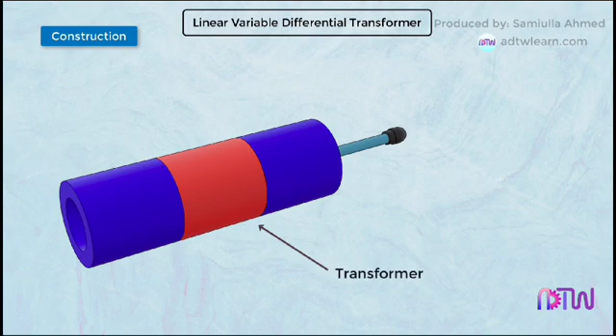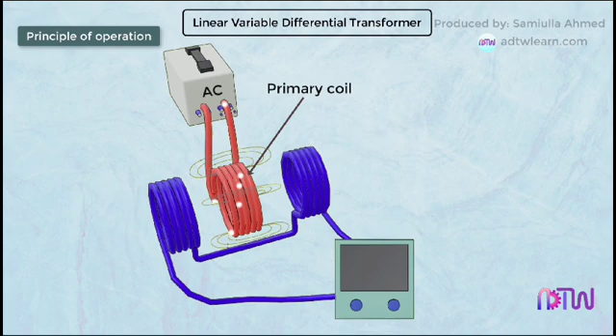Construction: a typical LVDT consists of a cylindrical transformer with a primary coil and two secondary coils, and a movable soft iron core. The primary coil is placed between the two secondary coils, with the soft iron core positioned between them. There is also a projecting arm attached to the soft iron core, which is used to measure displacement.